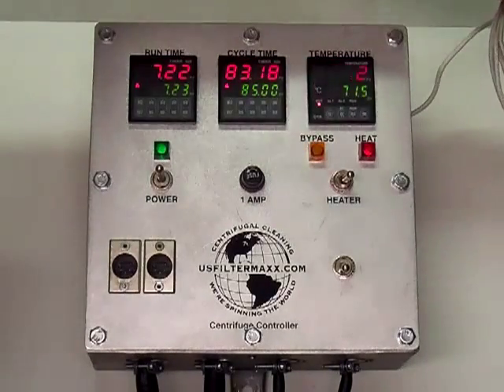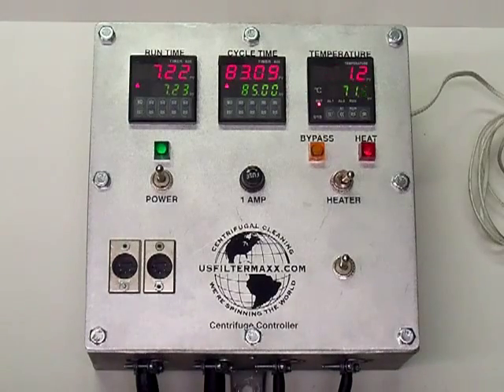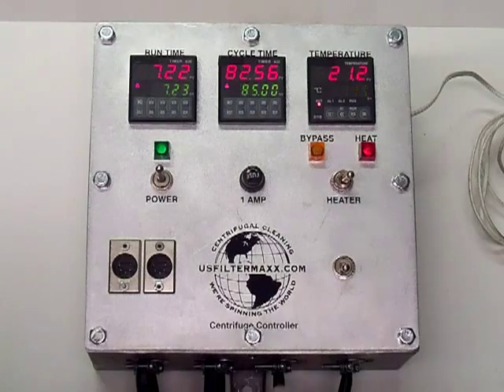We've got a probe here that goes into the actual heater unit — it says 'thermocouple' — that goes into the heater unit. This last button over here activates the run cycle for the variable speed controller. You can actually turn off the signal to the controller, which will power down the centrifuge, or turn it on and it'll run at a preset speed, which is adjustable. You can push it all the way up over 6000 G's if you want; standard is 3000 G's. That sums up the US Filter Maxx variable speed centrifuge controller.